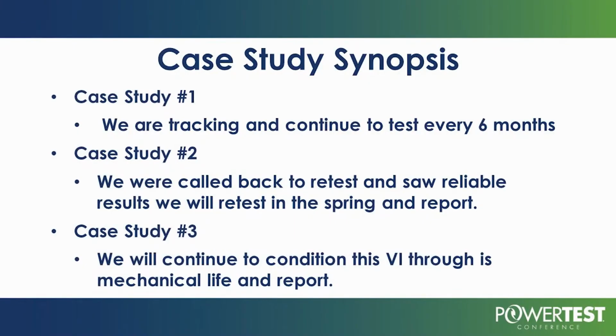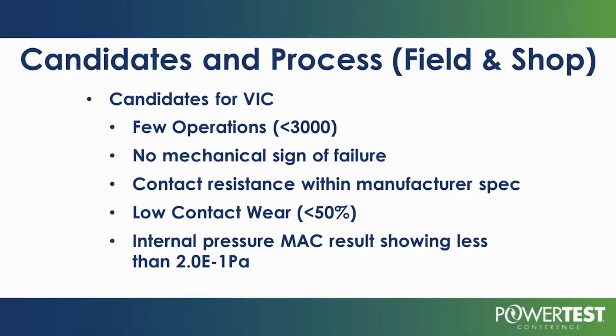Case 3 will continue to condition the VI through its mechanical life and try to keep this expensive generator breaker in service as long as possible for Portland GE. We need to talk about the candidates for conditioning. You can't really condition every breaker. We basically look at interrupters that have few operations, that have no mechanical sign of failure or fatigue, that have contact resistance readings within manufacturer specifications, that have low contact wear, and ones whose internal pressure is still far less than 1 PA. Now, in the 2 PA near failure interrupters, I think we can keep them in the 2 PA range for many, many years with this conditioning process.